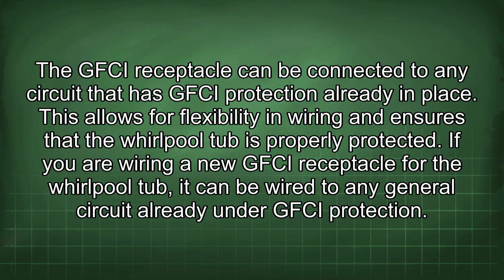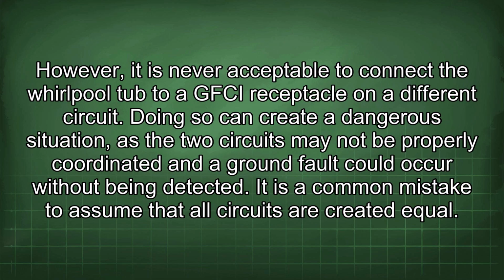If you are wiring a new GFCI receptacle for the Whirlpool tub, it can be wired to any general circuit already under GFCI protection. However, it is never acceptable to connect the Whirlpool tub to a GFCI receptacle on a different circuit. Doing so can create a dangerous situation, as the two circuits may not be properly coordinated and a ground fault could occur without being detected.